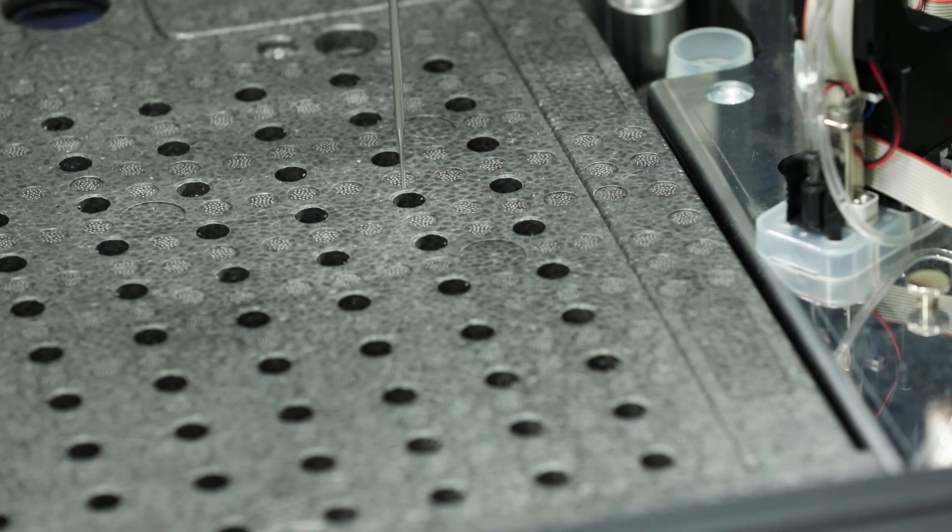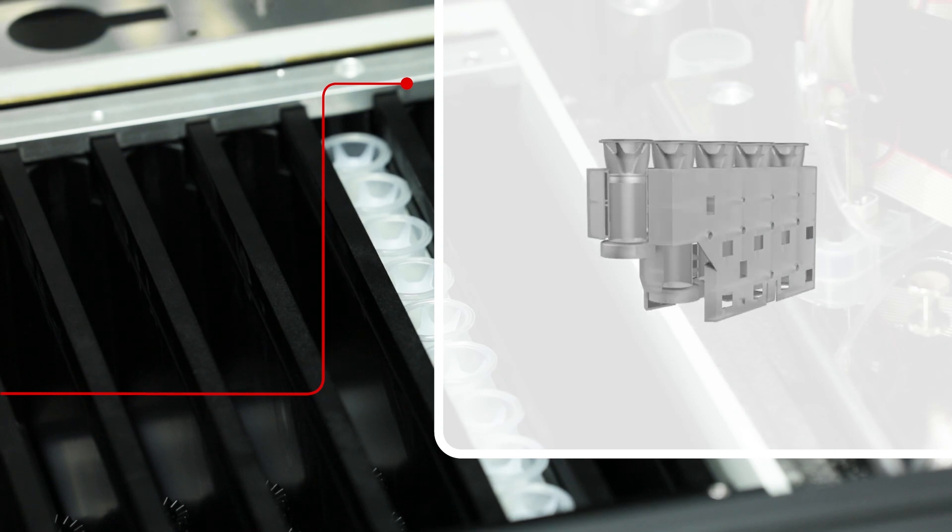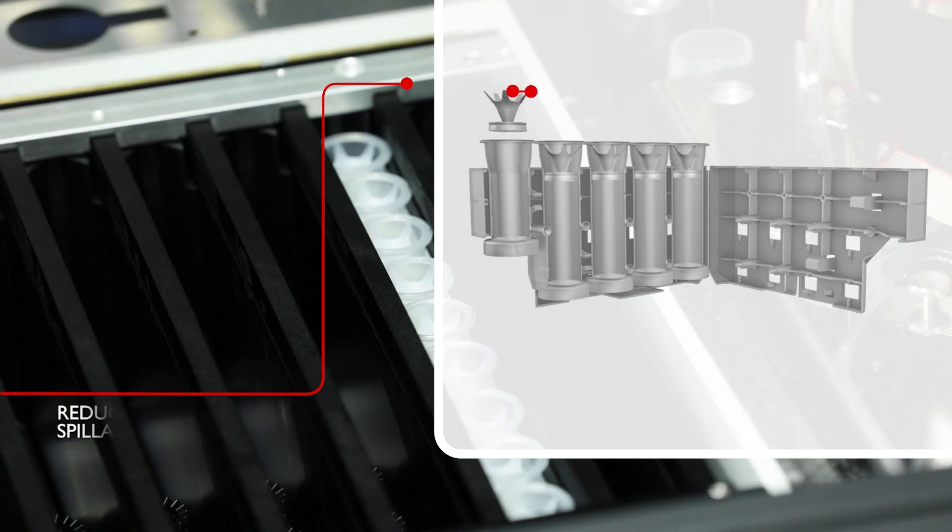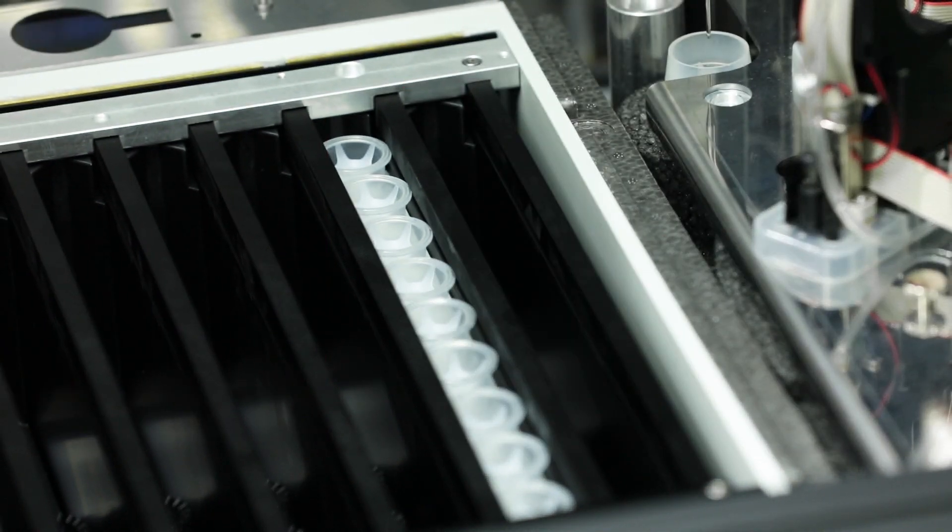Reagents for various detection methods are carried within a modular reagent cartridge. A total of five vials can be assembled in any configuration, providing multiple unique assay configurations. An innovative dynamic closing system improves reagent security and significantly reduces the risk of spillage and carryover.